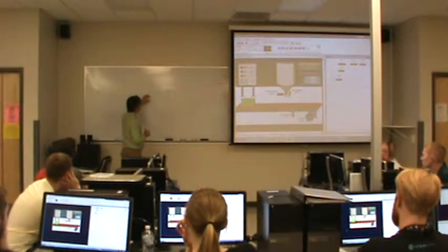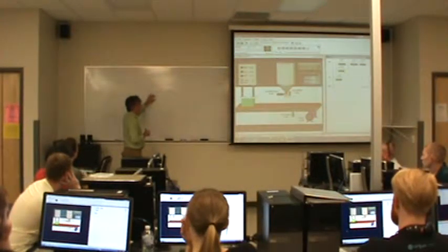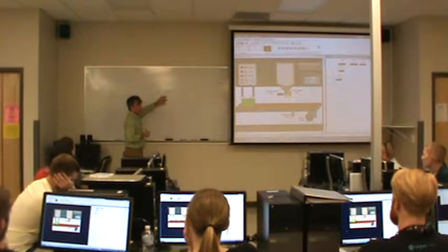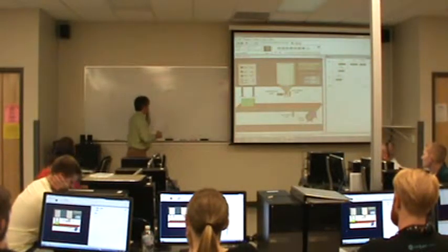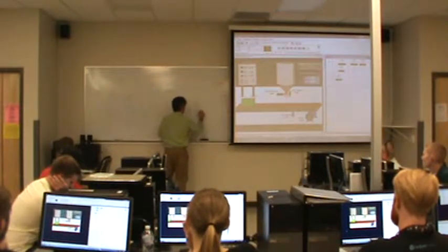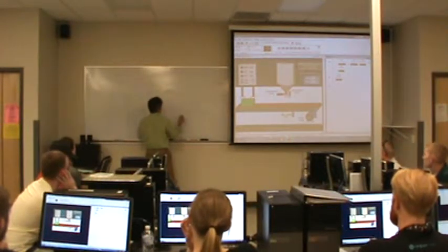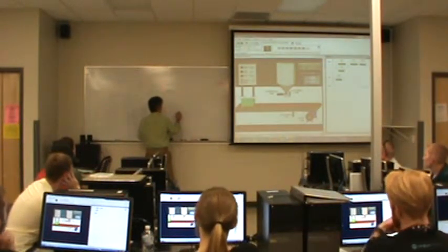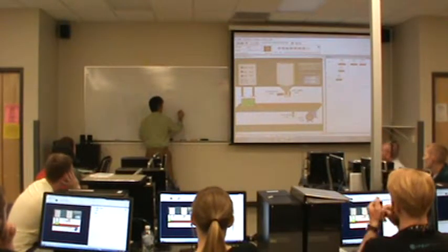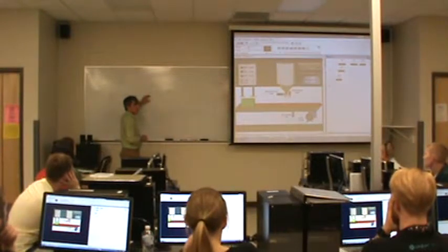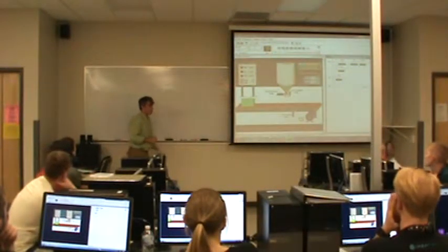If prox is off, then it doesn't matter whether level is on or off, right? It could be off, it could be on, we want the motor to be on. Okay? So to program this, what I might say is motor is the output. If prox is not true, motor should be on. That's basically what this says. Right? Prox not true, motor will turn on.